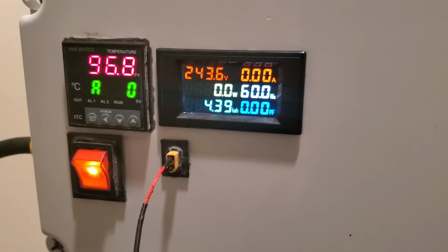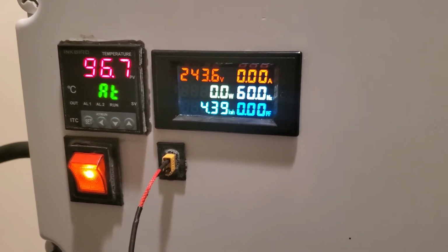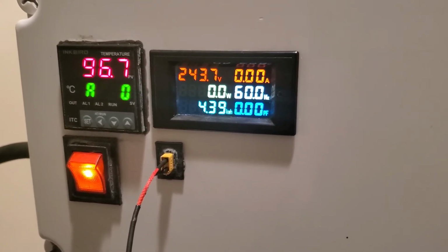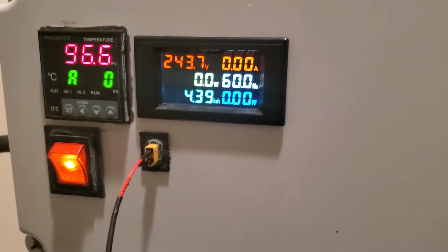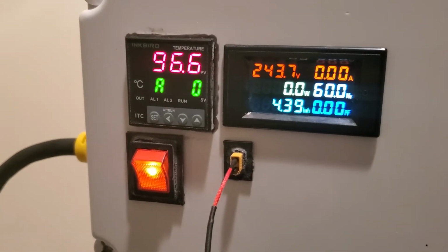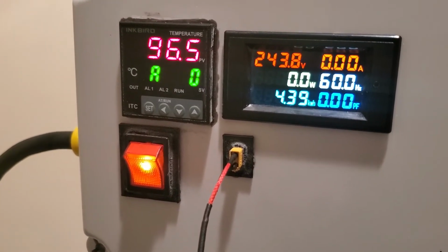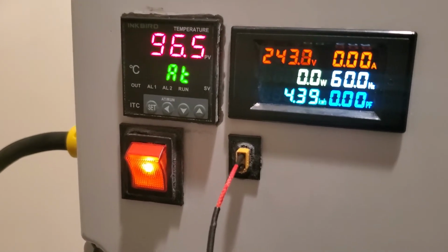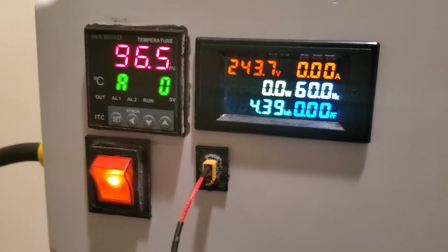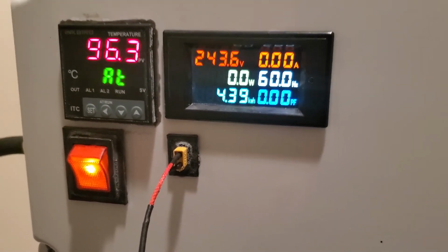And you probably want to do that with a process that is very similar to your end process. So if you change your setup, move your thermocouple, etc., you are going to have to recalibrate this controller. So again, if you want to get the InkBird ITC-100 into auto tune or auto calibration mode, you have to go into the setup and change the parameter CTRL to number 2. And we found this in an older InkBird manual that was on the internet, but not in the one that comes with the unit itself.